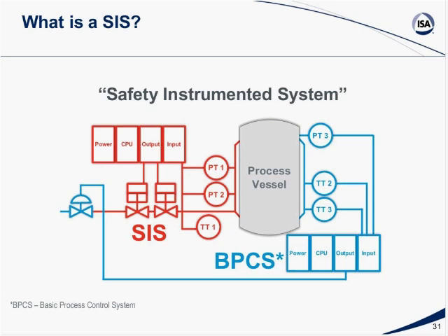The basic process control system controlling the process has all of these sensors tied into the control. So in this particular process, if the basic process control system is not able to control the process parameters, that's when the safety system also looks at those parameters and decides to take an action and bring the process to a safe state, because the process is currently in a pretty dangerous state. It needs to shut down your whole plant in a very safe and acceptable manner, so that it does not cause any accidents or explosions or damage to the environment, to people out there. That's basically the job of the safety instrumented system, where it acts in case of a dangerous condition where a process value really exceeds the set point or the normal operating conditions.